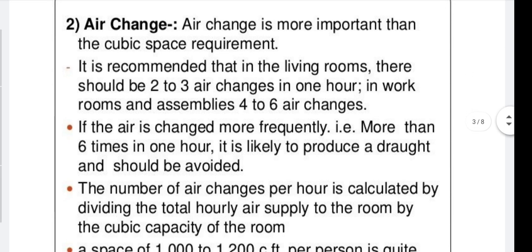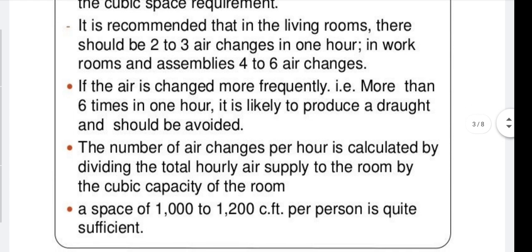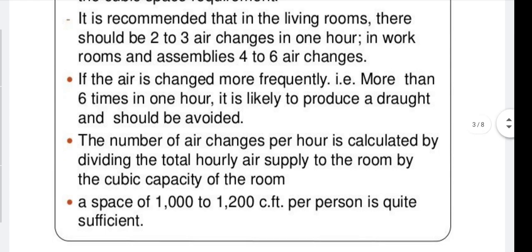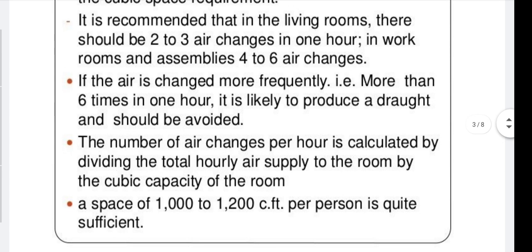Second standard: air changes. Air change is more important than the cubic space requirement. It is recommended that in living rooms there should be two to three air changes per hour; in workrooms and assemblies, four to six air changes. If air is changed more than six times per hour, it is likely to produce a draught and should be avoided. The number of air changes per hour is calculated by dividing the total air supplied to the room by the cubic capacity of the room. A space of 1000 to 1200 cubic feet per person is quite sufficient.